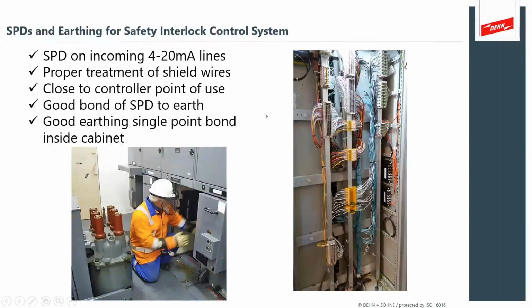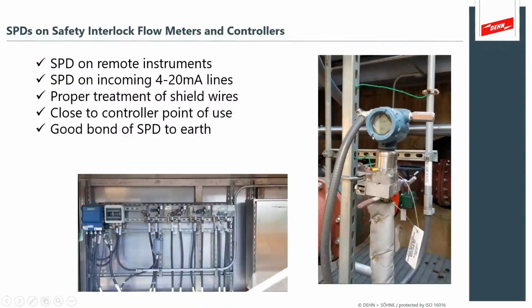Safety interlock systems. This is one of the areas that are mandated by the standards. So it's an important aspect that you can bring into your maintenance plans, into your inspection systems, where you're monitoring your intrusion alarm and you're making sure that the system is properly surge protected as part of its maintenance cycle. So these are the things we check the system for. SPDs on the low voltage, proper treatment of the shield, close as possible to point of use, good bonding systems, good cabinet earthing systems installed where you can clearly see the bonding conductors. Flow meters, this is a nice photograph showing the actual surge protection device installed at the flow meter point of use, properly dealing with the shield and the grounding wire systems with solid connections back to earthing bus bar control.